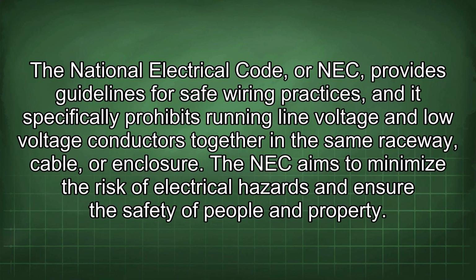The National Electrical Code, or NEC, provides guidelines for safe wiring practices, and it specifically prohibits running line voltage and low voltage conductors together in the same raceway, cable, or enclosure. The NEC aims to minimize the risk of electrical hazards and ensure the safety of people and property.